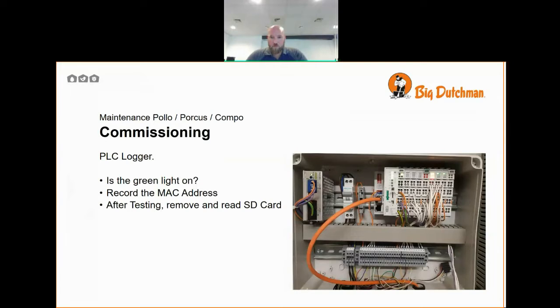Record the MAC address that's on the PLC, and after completing the full site acceptance test, you can remove the SD card and read the file under the program Microsoft Excel. As long as there have been details recorded and that these are correct, you know that the logger is going to continue to log the data as required.